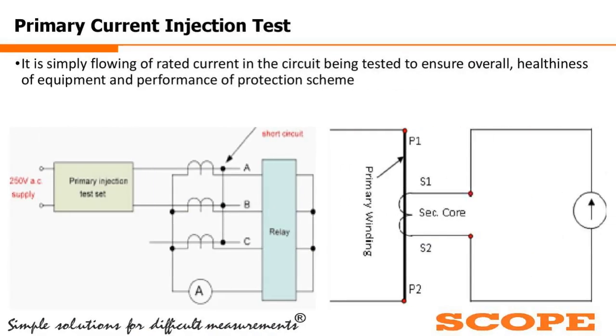The basic idea is that we need to flow a rated current in the circuit we need to test, to ensure or check the overall healthiness of the equipment and to check the performance of the protection scheme. Here you can see the primary testing equipment is connected directly to the primary side of the CT — that is P1 and P2 — and we inject the rated current from the primary side. After that we check the secondary current from the secondary side of the CT to ensure its healthiness. This same approach applies for circuit breakers and relays as well.